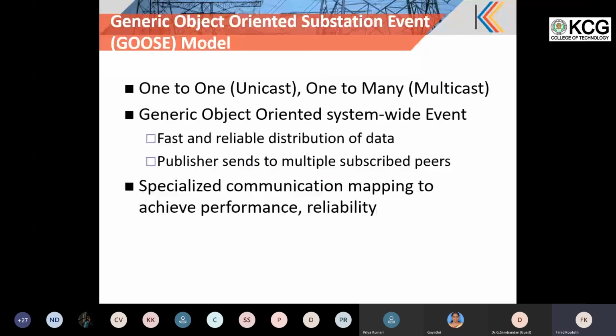Now moving on to the Generic Object Oriented Substation Event, GOOSE model. It is similar to report, but as I mentioned, report is based upon the MMS. It uses TCP/IP to send the data out, but GOOSE is generally a publish-subscribe kind of scenario. It is multicast onto the Ethernet network itself, so it is a fast and reliable distribution of the data. Publisher sends the data, multiple subscribers can receive the data in GOOSE, and it is highly reliable, fast delivery is guaranteed in this.